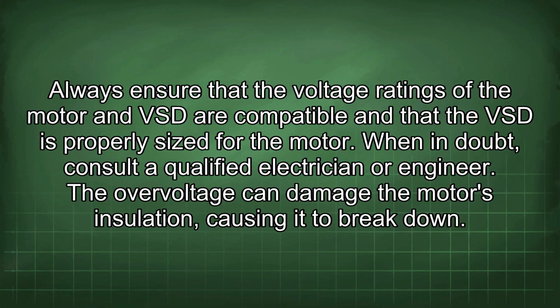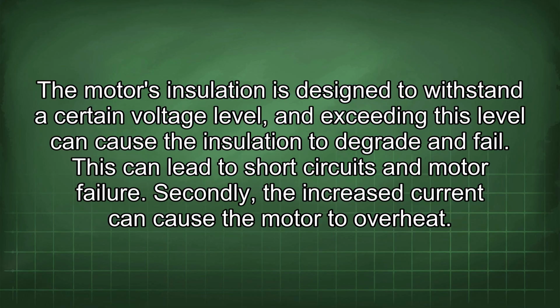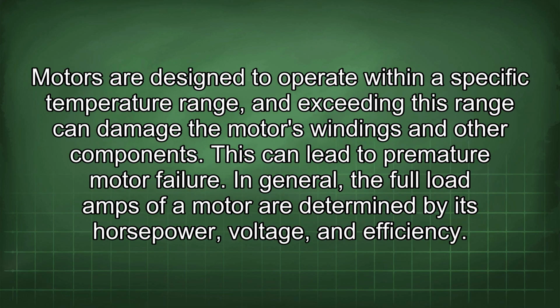The overvoltage can damage the motor's insulation, causing it to break down. The motor's insulation is designed to withstand a certain voltage level, and exceeding this level can cause the insulation to degrade and fail. This can lead to short circuits and motor failure. Secondly, the increased current can cause the motor to overheat. Motors are designed to operate within a specific temperature range, and exceeding this range can damage the motor's windings and other components. This can lead to premature motor failure.